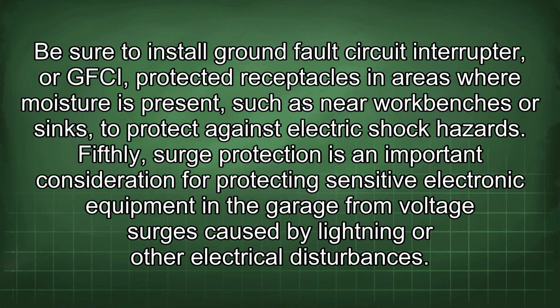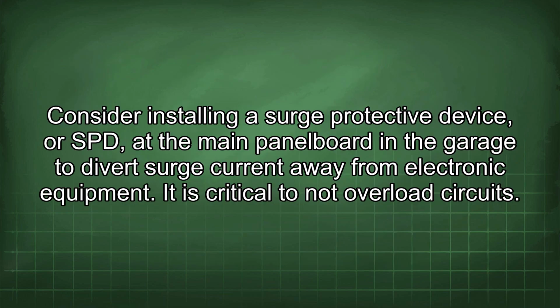Fifthly, surge protection is an important consideration for protecting sensitive electronic equipment in the garage from voltage surges caused by lightning or other electrical disturbances. Consider installing a surge protective device, or SPD, at the main panel board in the garage to divert surge current away from electronic equipment. It is critical to not overload circuits.